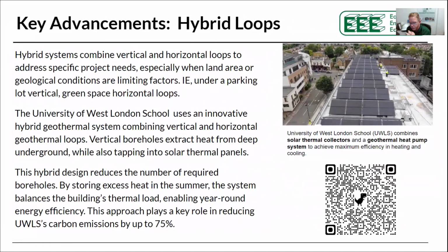So what I mean by that is you could go into an application, say you've got a MURB application, a 30-story MURB building with a parking lot out front. You might put some of the ground loop underneath the parking lot, but it's not quite enough to take care of the building. So if you have green space next to the building, you can combine a vertical and a horizontal loop, using green space as well as under the parking lot, to cut back on the space required.